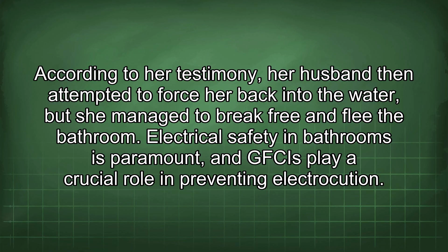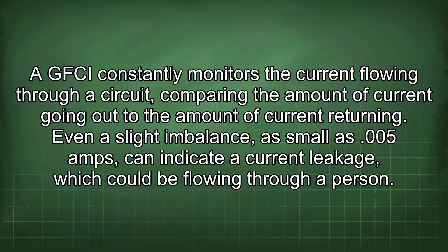Electrical safety in bathrooms is paramount, and GFCIs play a crucial role in preventing electrocution. A GFCI constantly monitors the current flowing through a circuit, comparing the amount of current going out to the amount returning. Even a slight imbalance, as small as .005 amps, can indicate a current leakage, which could be flowing through a person. When a GFCI detects such an imbalance, it trips the circuit, cutting off the electricity in as little as 1/40th of a second.